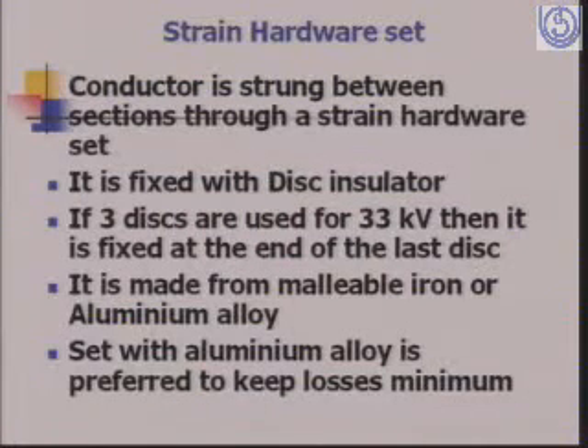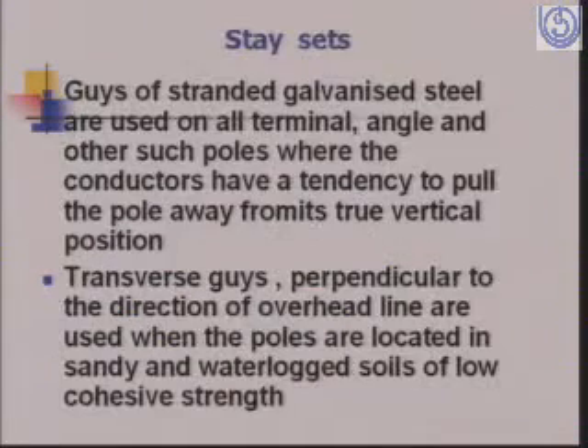Then the next item used is a strain hardware set. The conductor is strung between sections through a strain hardware set. It is fixed with the disc insulator. If 3 discs are used for 33 kV, then it is fixed at the end of the last disc. It is made from malleable iron or aluminium alloy, and a set with aluminium alloy is preferred to keep losses minimum.